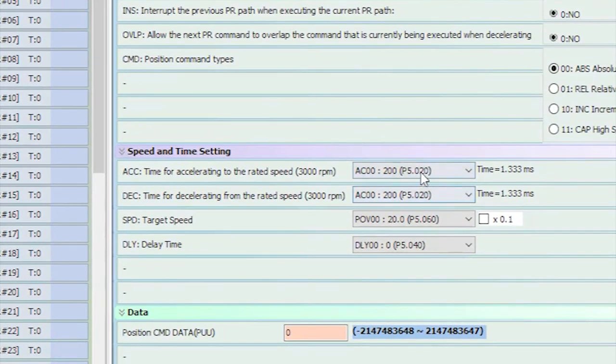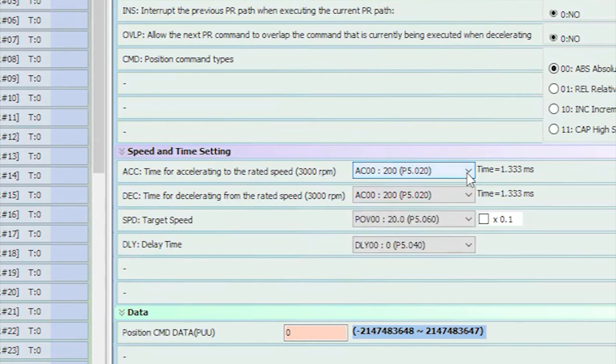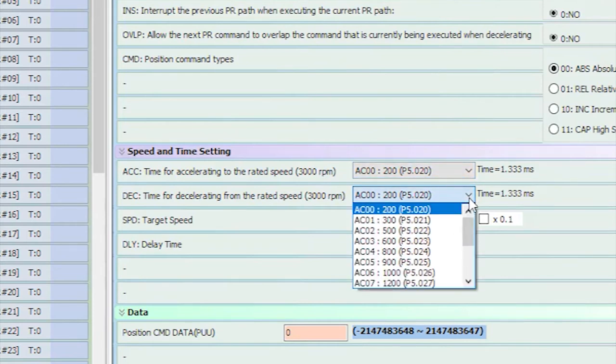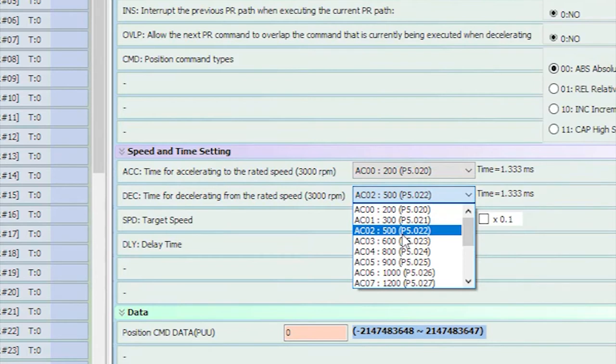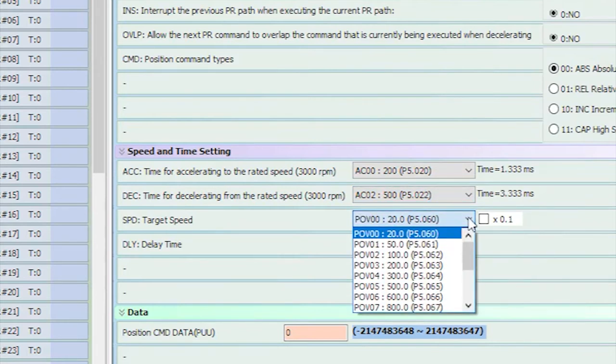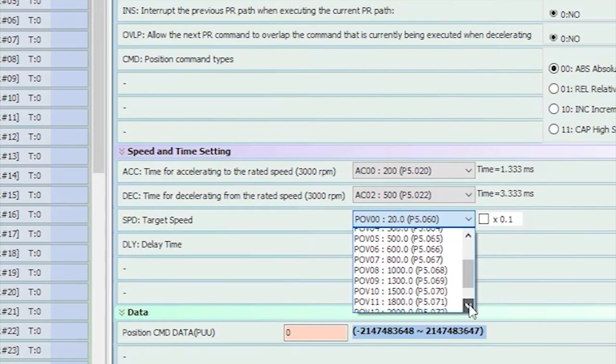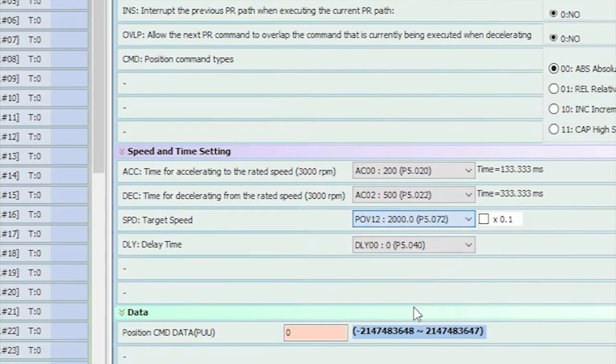Down here we set up how the move will go. This guy pulls from the 15 line ramp table, 200 milliseconds is fine for now, and a deceleration pulls from the same table. Let's grab 500 milliseconds for that one. The speed pulls from the speed table. Again, we will just grab one of the defaults. I know around 2000 RPM will work fine for this slide.